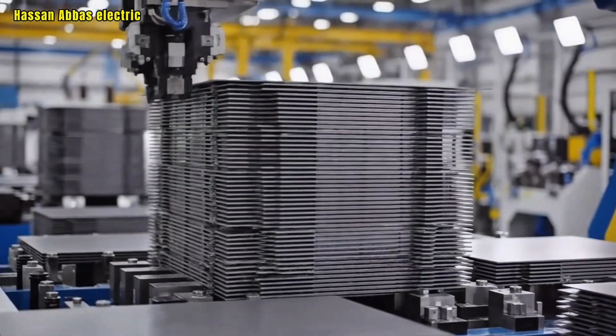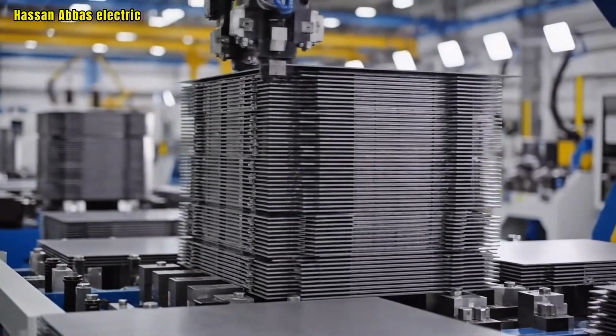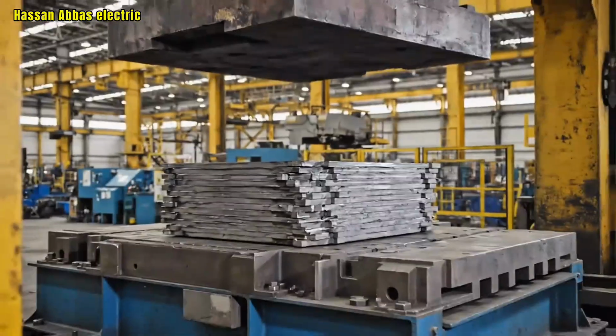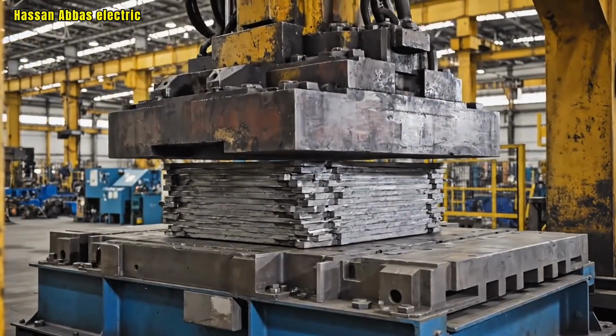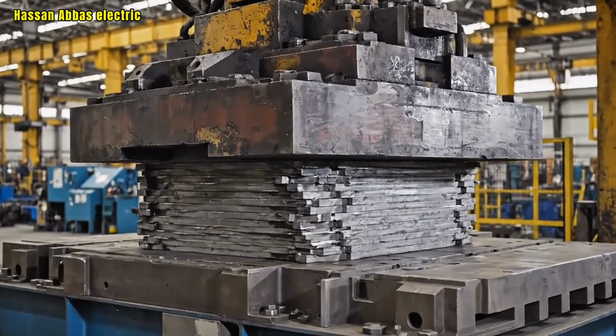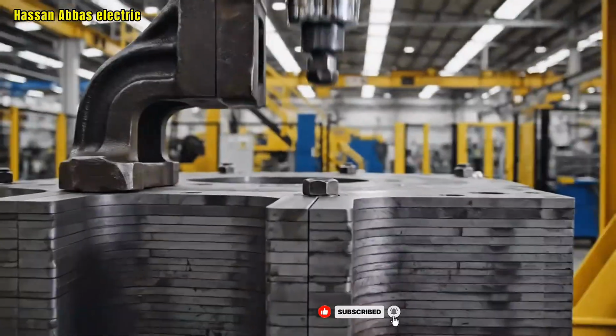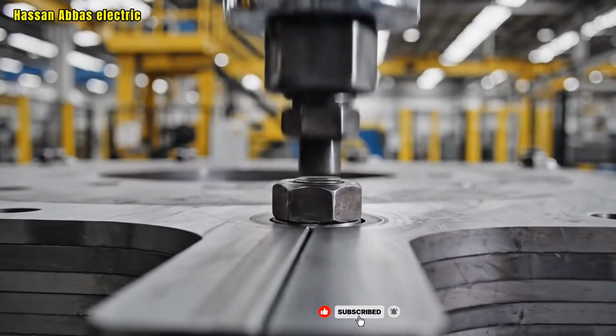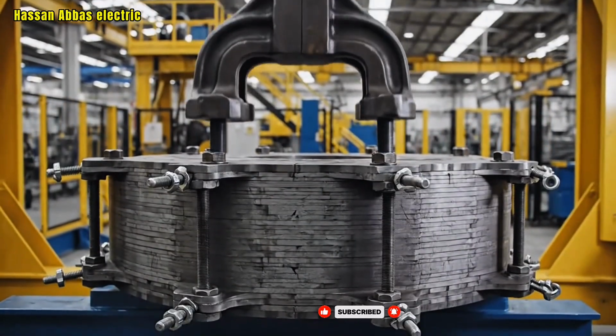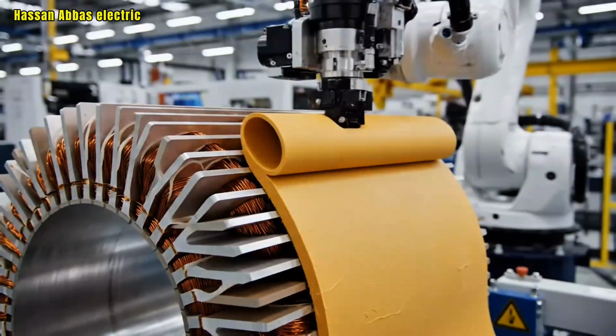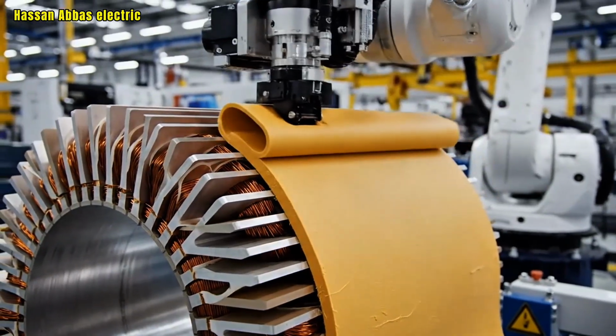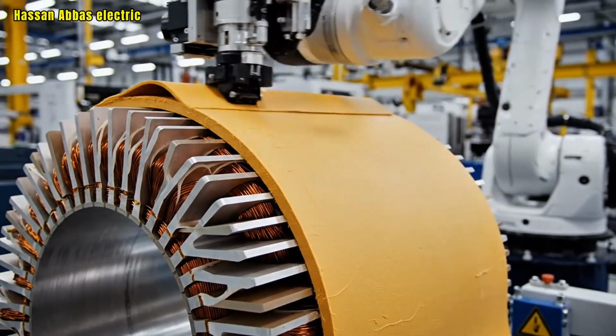Laminations are stacked to build the transformer magnetic core. The core stack is compressed to increase strength and stability. Core clamps are installed to lock laminations firmly together. Insulation is added to protect windings from the metal core.